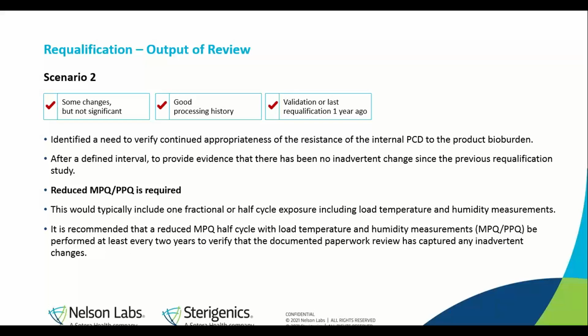This would identify a need to verify the continued appropriateness of the resistance of the internal PCD to the product bioburden. After a defined interval, this would provide evidence that there has been no inadvertent changes since the previous qualification study. In this scenario, a reduced MPQ or PPQ may be required. This would typically include 1 fractional or half cycle exposure. Within that 1 fractional or half cycle, what should be included is a load temperature and humidity measurement.